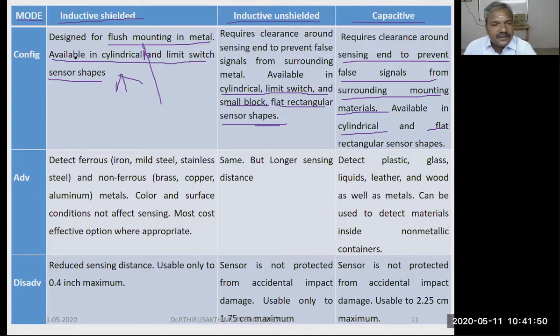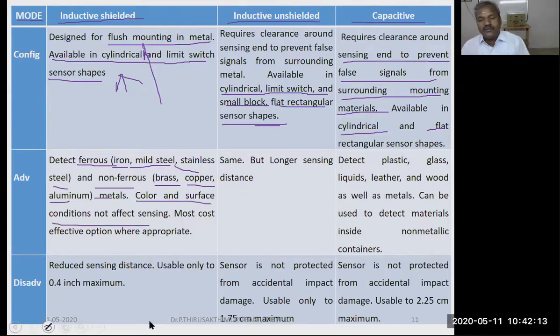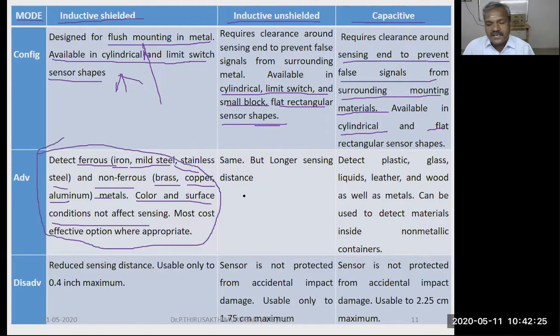The advantage of the inductive shielded type is that it detects iron, mild steel and stainless steel, which are ferrous, and non-ferrous metals like brass, copper and aluminum. Color and surface conditions do not affect sensing. It is the most cost-effective option. The same applications apply to the unshielded type, but the unshielded type has a longer sensing distance.